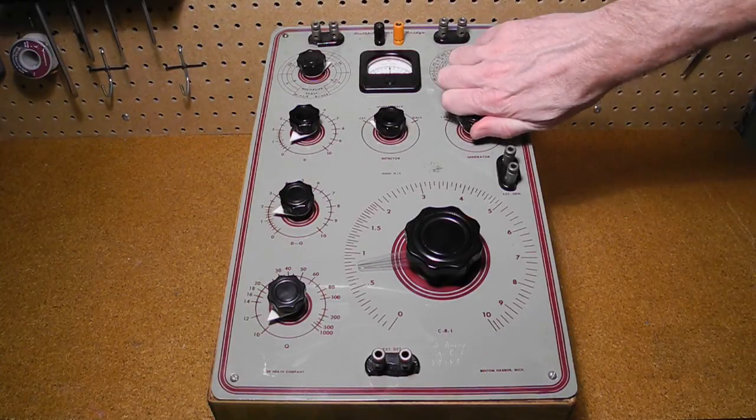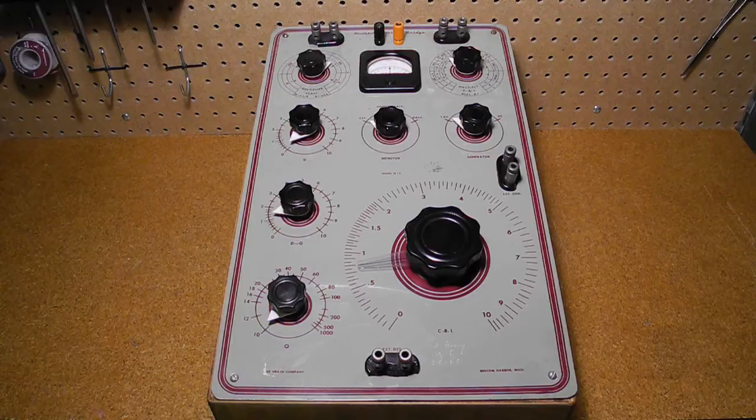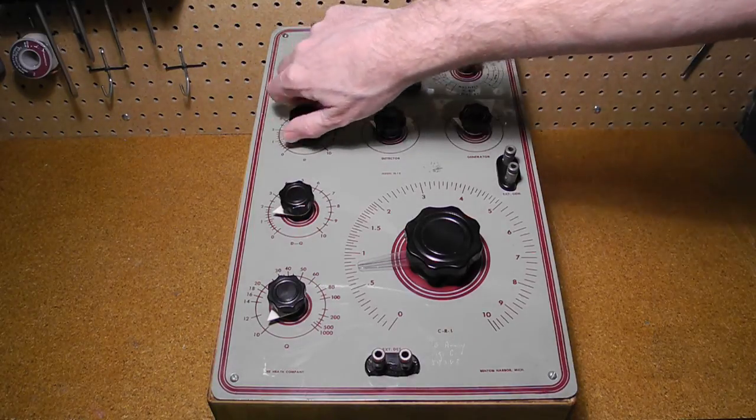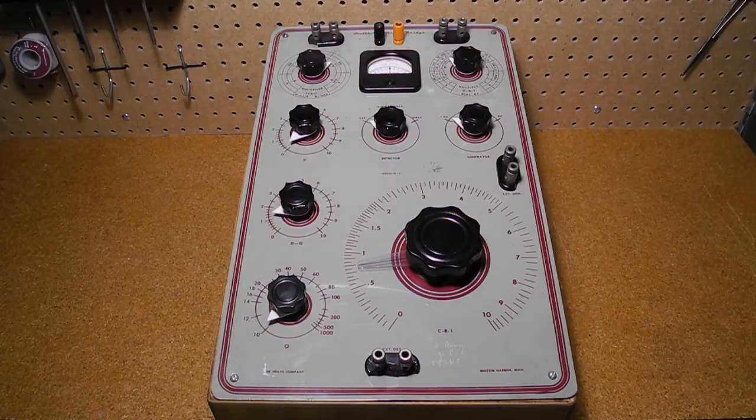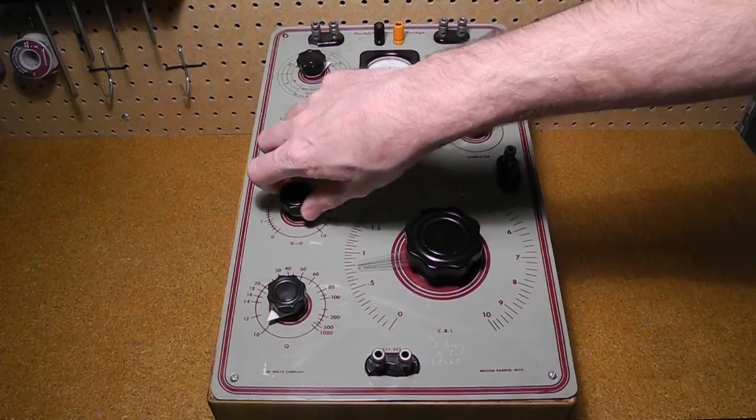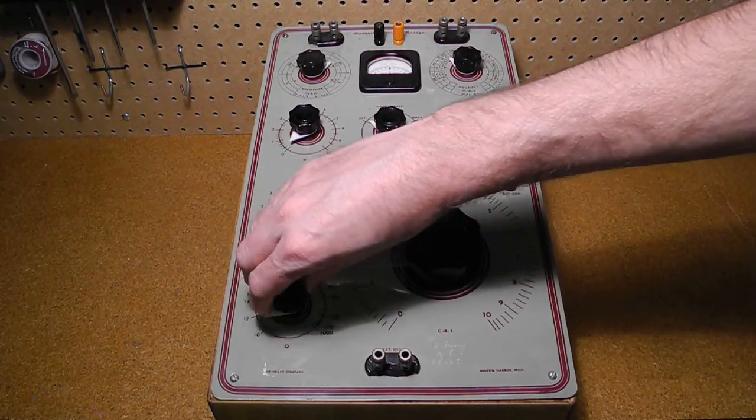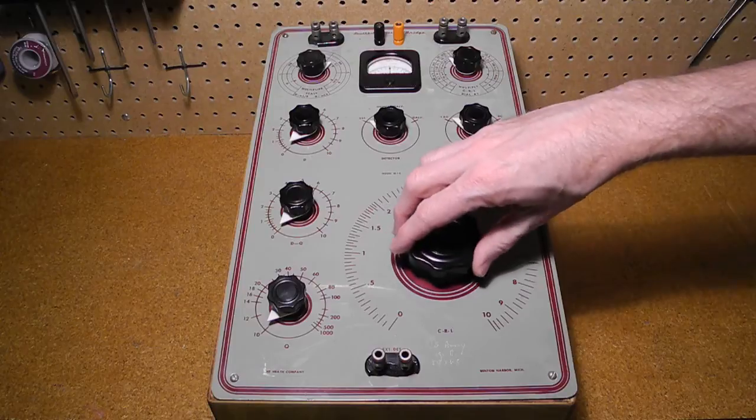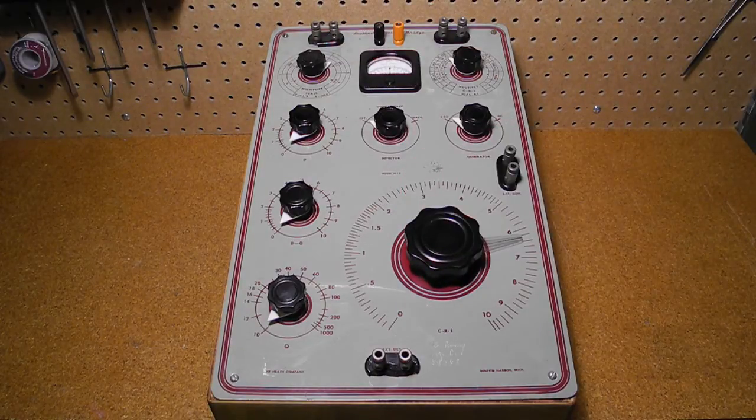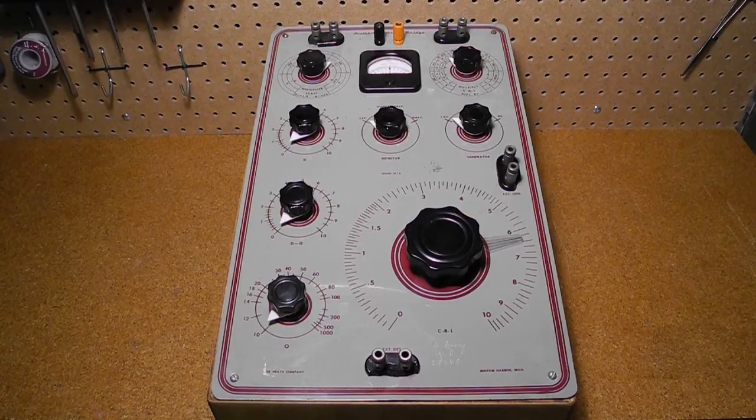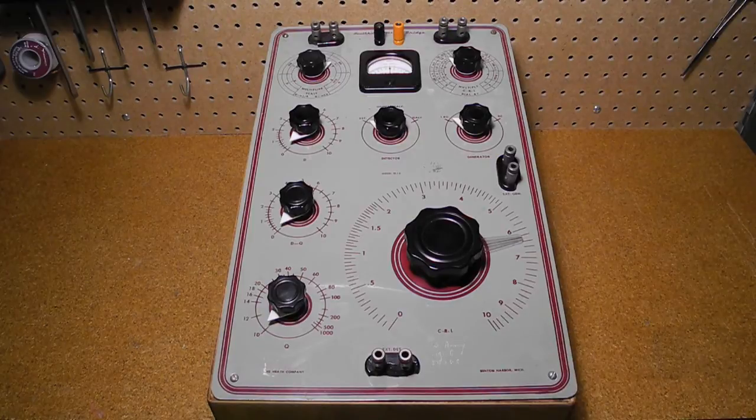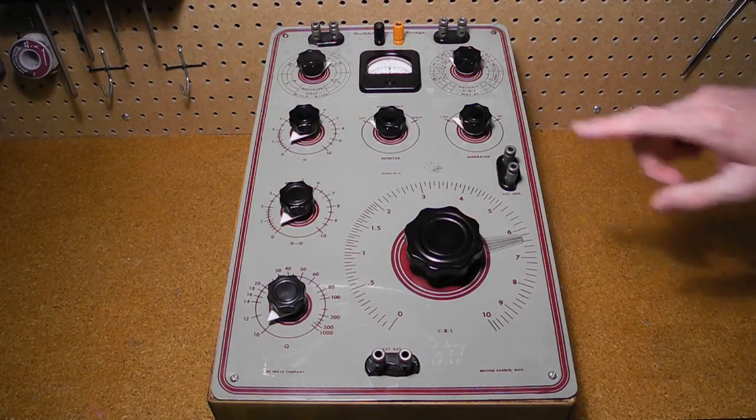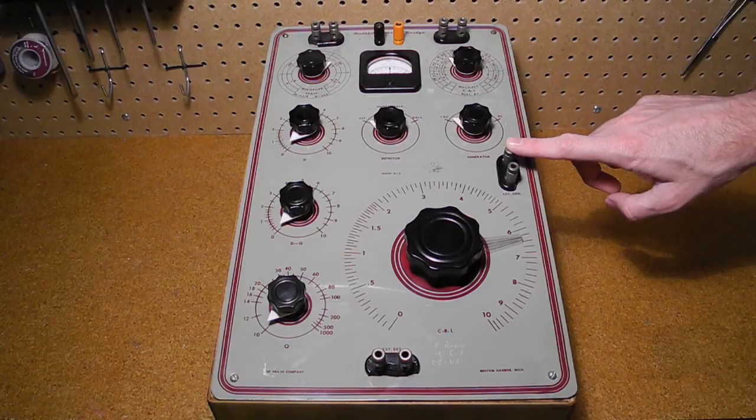To the right is the selector for the generator, either the internal 1kHz Hummer, an external generator connected to the EXT GEN jacks, or DC from the battery. To the left is the selector for measuring dissipation factor used when the mode is set to D. Below that is the selector for balancing dissipation factor or Q when the mode is set to DQ. And below that is the selector for balancing Q when the mode is set to Q. The large knob labeled CRL is for balancing the bridge when measuring capacitance, resistance, and inductance. The component value is read from this dial, so it's made quite large. The jacks at the bottom are for connecting an external detector for AC measurements, typically a set of sensitive high impedance headphones. To the right is a connector for an external signal generator, which I'll describe later during the demo.